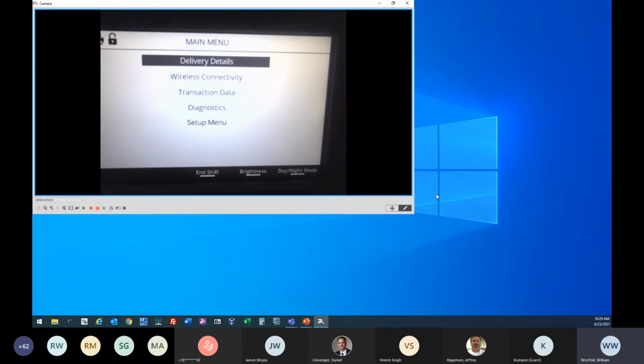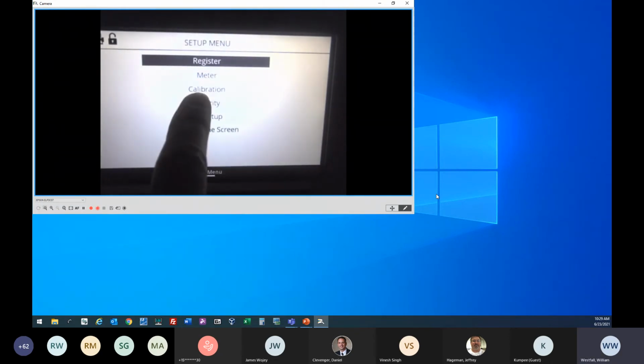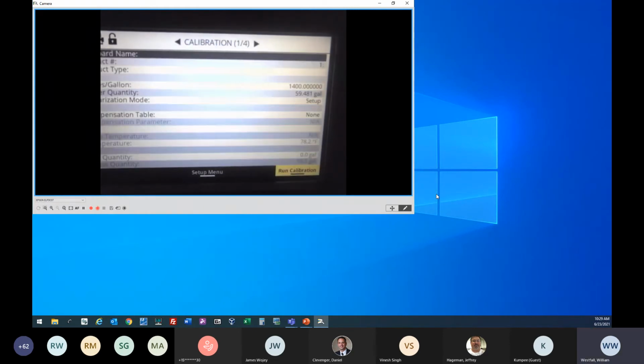Okay, so once we are in calibration, it's pretty much the same process on the IQ as it is for the LCR2, just a little bit different as far as the keystrokes and the menu. Once you get into the main menu, you see main menu up at the top. We want to go into the setup menu, so you can hit the up arrow once to get there. Hit the OK key, and then you're in the setup menu. What we want to go to is this calibration menu right here.